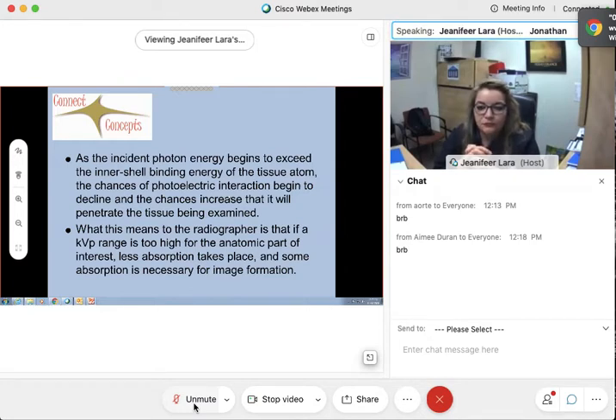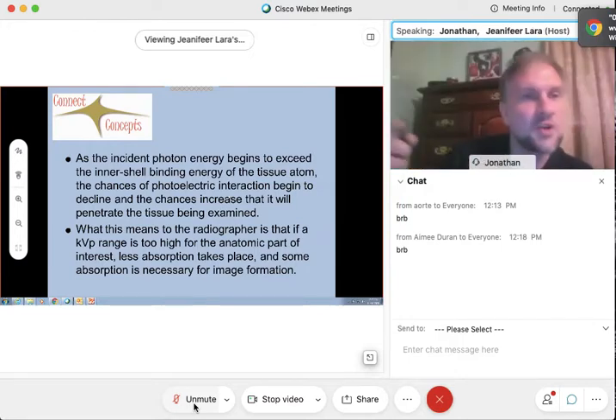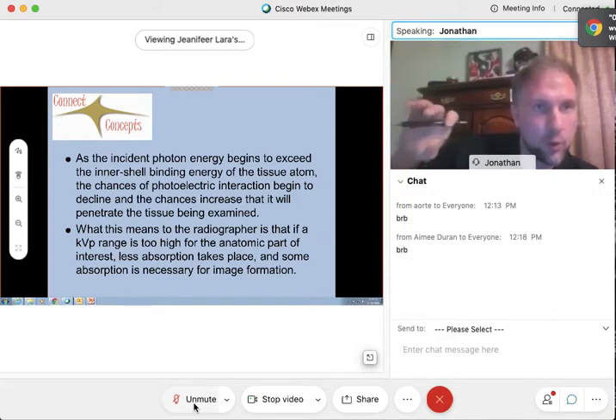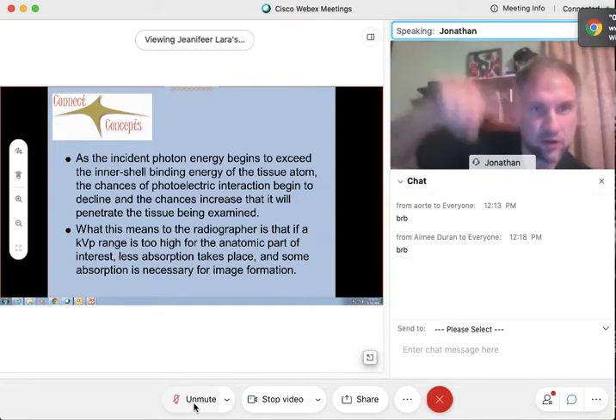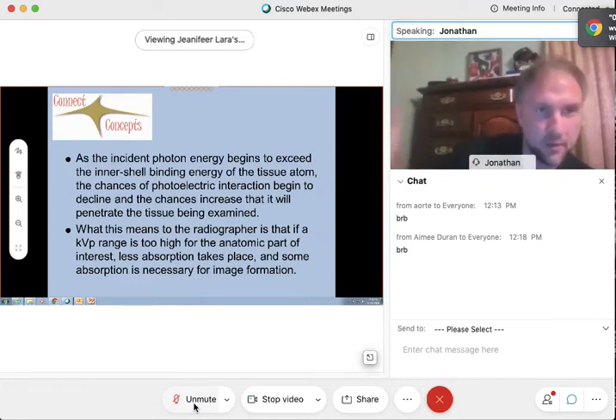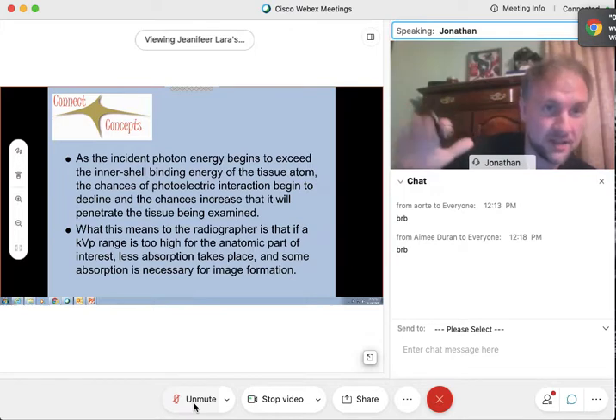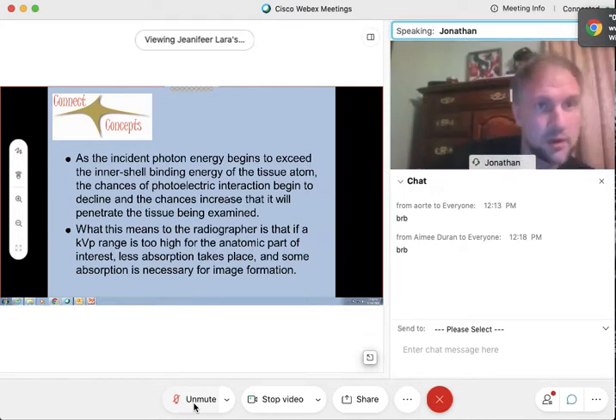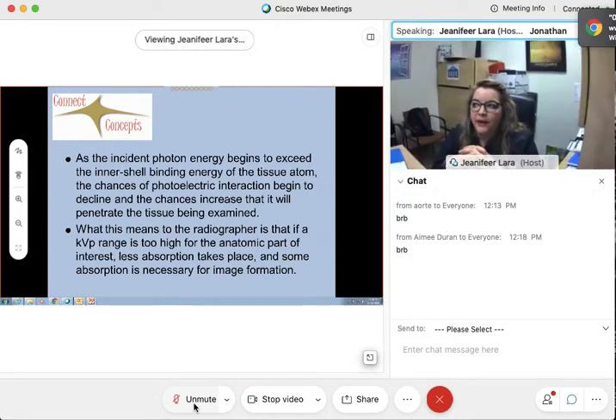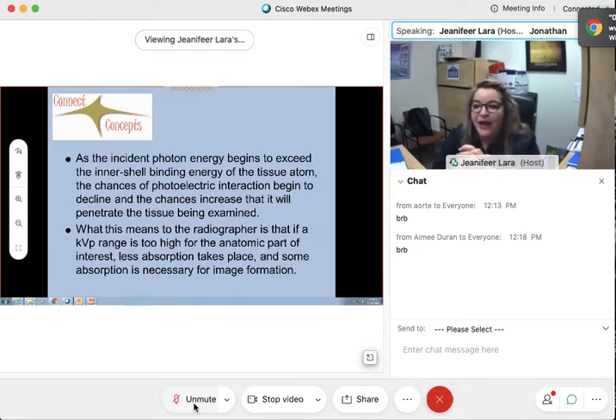When do we want absorption? When do we want more absorption, more transmission, more Compton — that's what we're trying to regulate. Can you have a 30 keV photon that just happens to miss the outer and middle shell and strike an inner shell but it's not strong enough? You can have all types of interactions, but what you care about is the two major interactions that cause image formation.